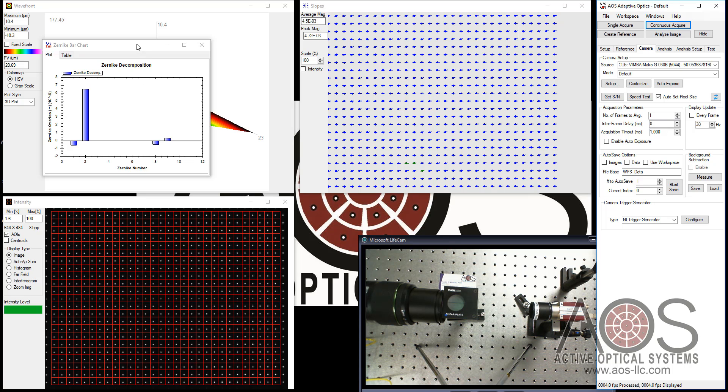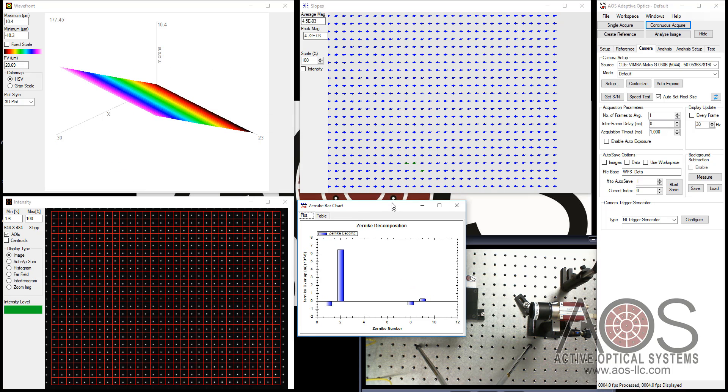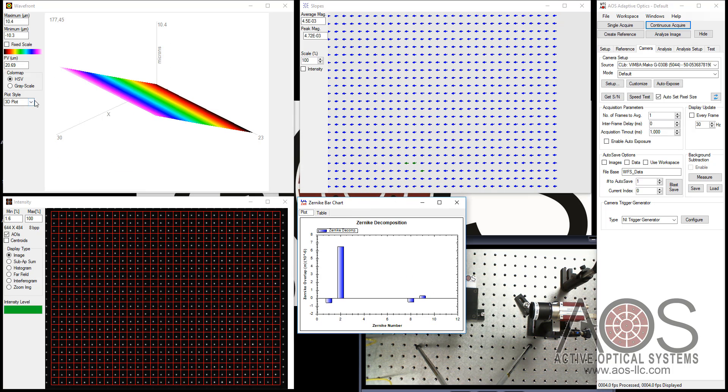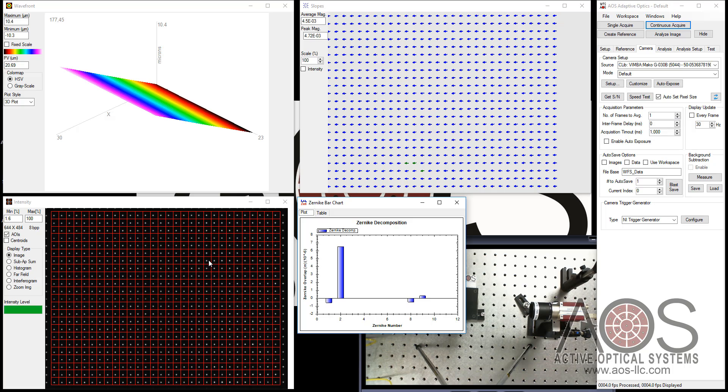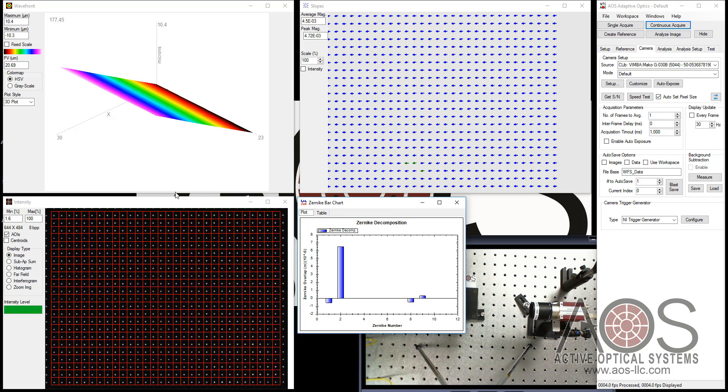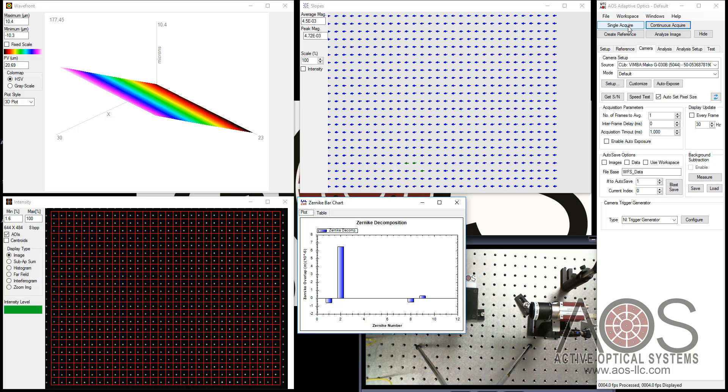You have two options on calibration. One is to load a calibration that was provided with the wavefront sensor. All of the wavefront sensors come with a factory calibration. This will allow you to make a measurement relative to a very flat wavefront. The other option is to create your own array of AOIs. This is especially useful when you're doing a relative measurement like we're going to try today.